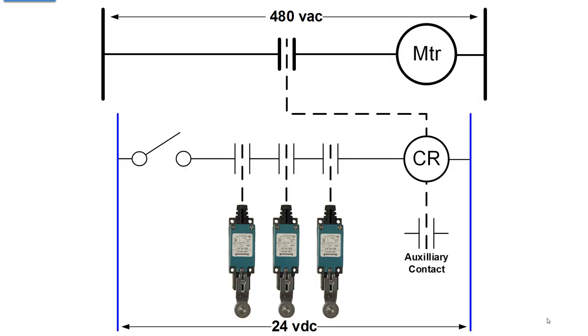Replace all of that with one contact, and that one contact is a heavy-duty contact from a contactor coil which we're labeling CR, control relay, and we've moved those four conditions down into a low voltage 24 volt DC circuit, and now these four sets of contacts can be very small and lightweight. 150 milliamps is considerably less than 7 amps.